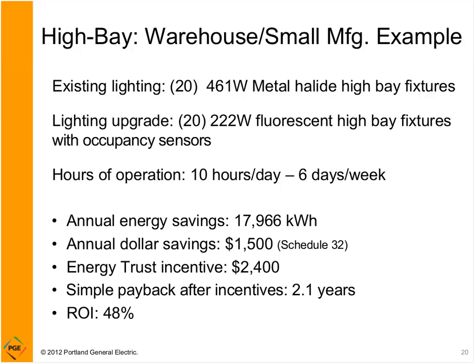So what we have here is a high bay replacement example. It could be in a warehouse or maybe small manufacturing, even retail. Existing lighting: 20 461-watt metal halide high bay fixtures. It's really using like a 400 watt lamp, factoring the ballast in; that's the actual wattage of the fixture. Upgrading and replacing those fixtures with 20 222-watt fluorescent high bay fixtures with occupancy sensors, if it's appropriate for the space, and a lot of times it is.